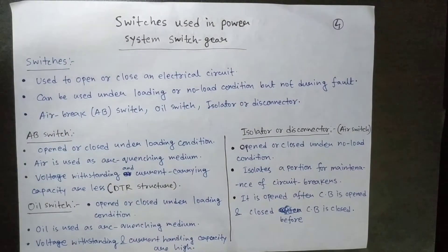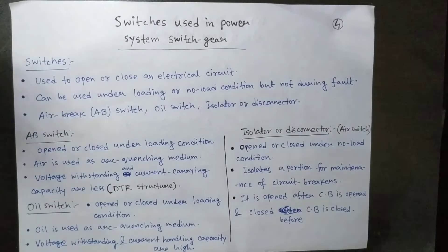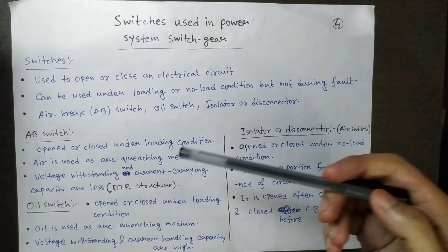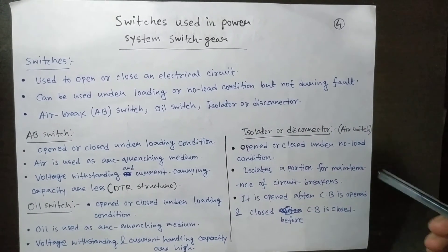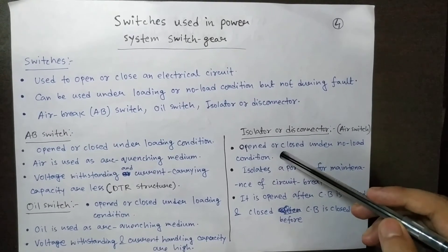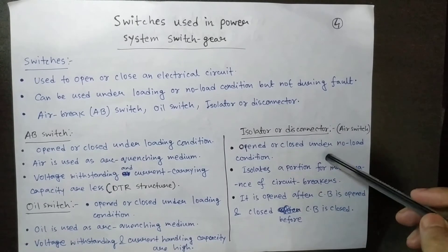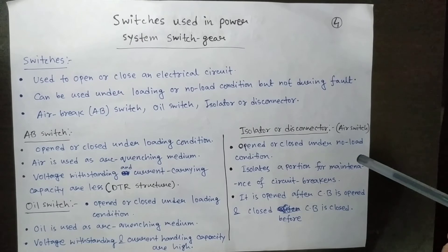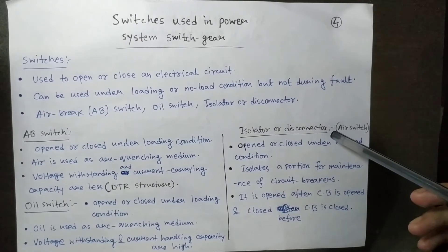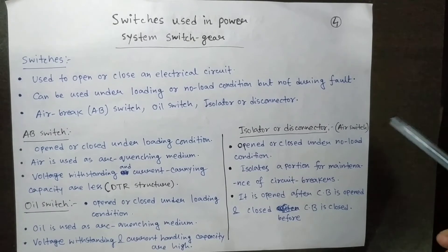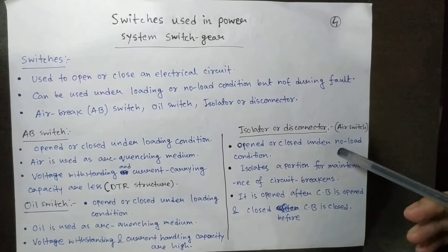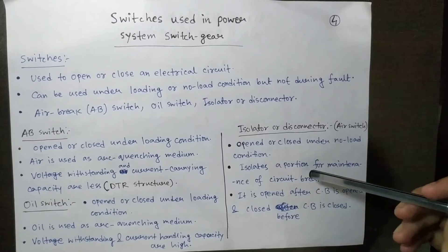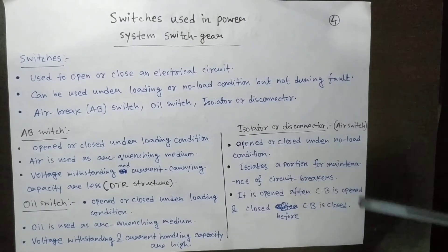Now the isolator, or disconnector, is also a kind of air switch. Sometimes the terms isolator and AB switch are used interchangeably, but there is an important difference: the isolator can only be used during no-load conditions. It can never be used under loading conditions. It is used to isolate a portion of the circuit for the maintenance of circuit breakers.